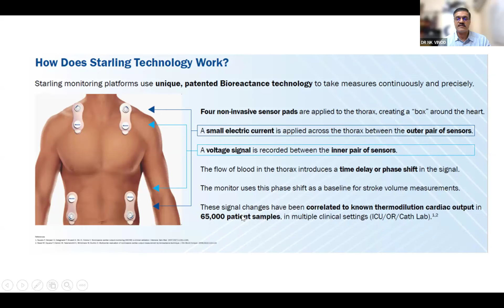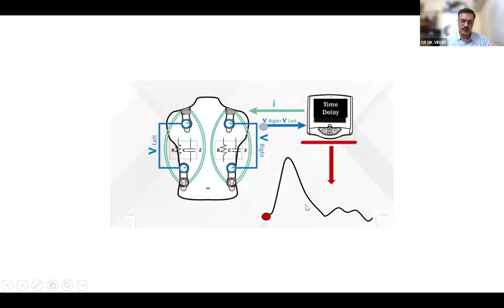These signal changes have been correlated to the known thermodilution cardiac output monitoring in 65,000 patient samples in many clinical settings, like in the ICU, operating theater, or the cath lab. So the bioreactance assesses the pulsatile flow-induced frequency modulations and phase shifts in voltage across the thorax. And there's a 100-fold reduction in the impact of extraneous electrical fields on the cardiac output estimates. A non-invasive cardiac output measurement signal is determined separately from each side of the body, and the final cardiac output is obtained as an average.